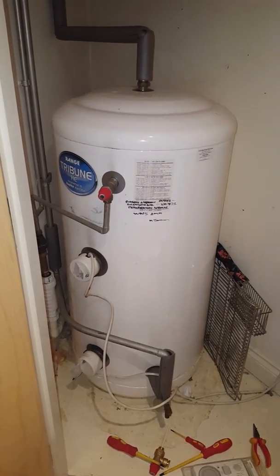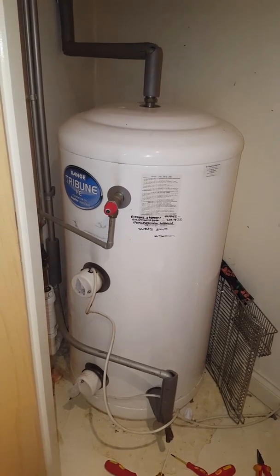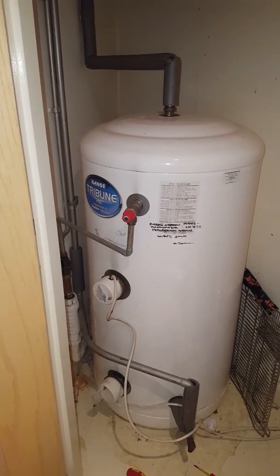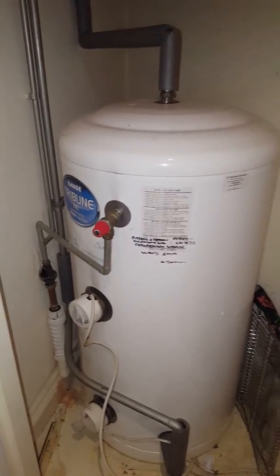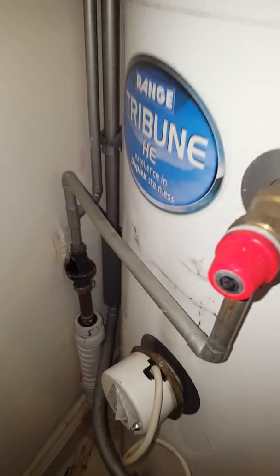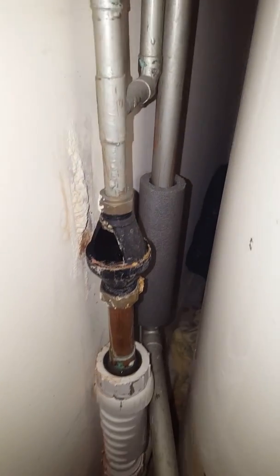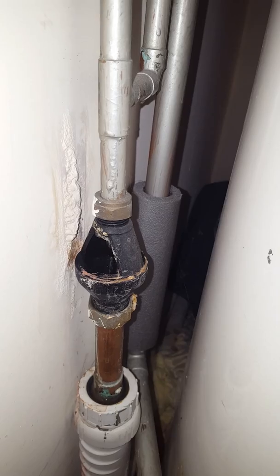My name is Tony Morgan from A&R Boilers, members of the NGNAT network. The problem we've got is no water on this electric unvented hot water cylinder. What's happening is you can hear the water dribbling — it's leaking out of this valve here into the tundish. You can hear it running like that, so if you have this problem where you can hear the water running like this...